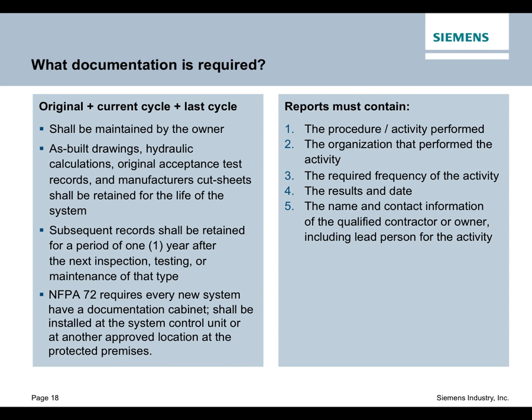So now it's time for the documentation. So we've thought about it, we understand the value, the need, we've kind of got an idea of how these things come together in the code, and now we're getting the right people to do the work, and now we're going to get documentation to show that the work has been done. And there's a couple of important critical statements that need to be made here. First of all, that second bullet on the left-hand side, that all as-built drawings, hydraulic calculations in the area of fire sprinklers, the original testing records, cut sheets shall be retained for the life of the system. It's very important to realize that. Subsequent records, these would be the annual, semi-annual testing and maintenance of the system, can be retained for a period of 1 year after the next inspection.